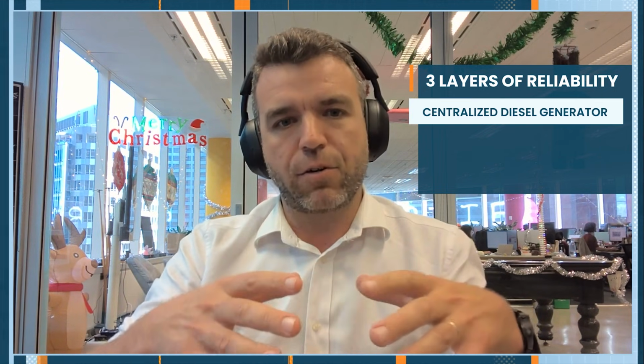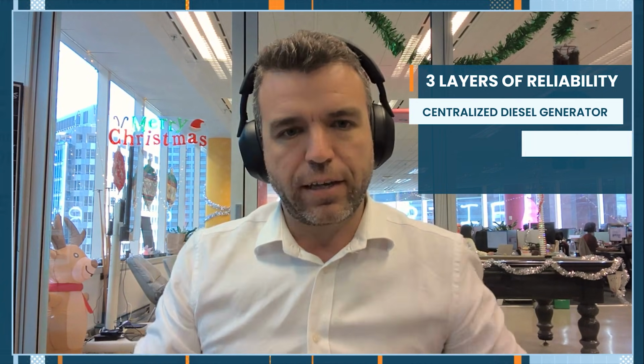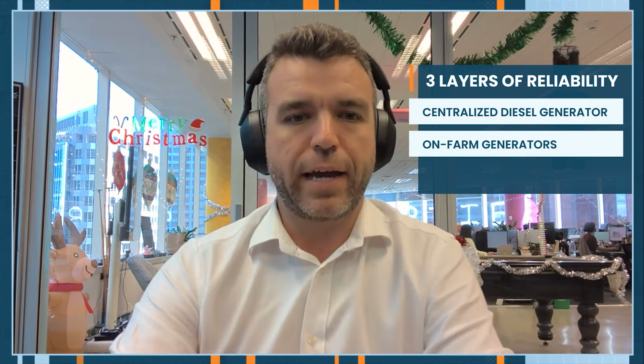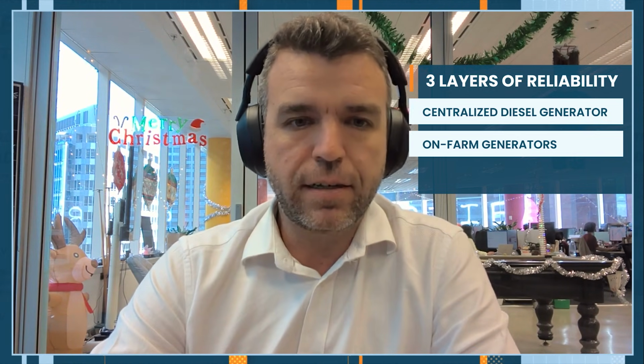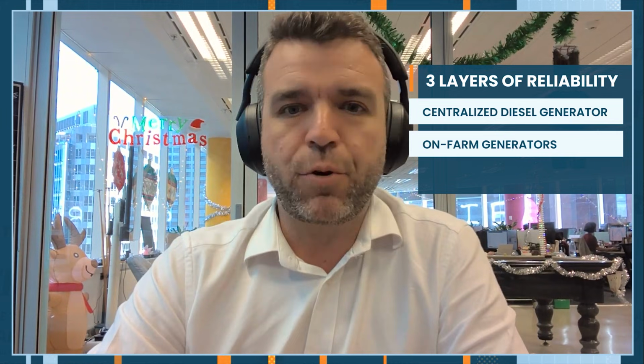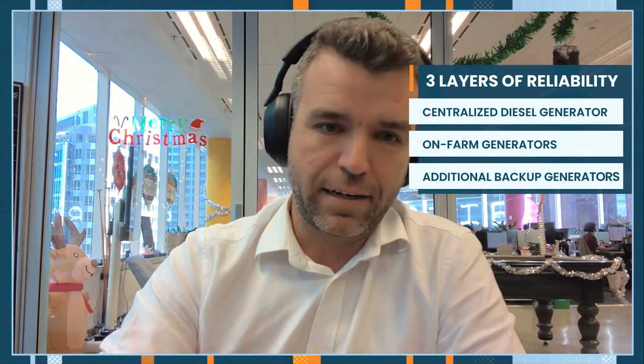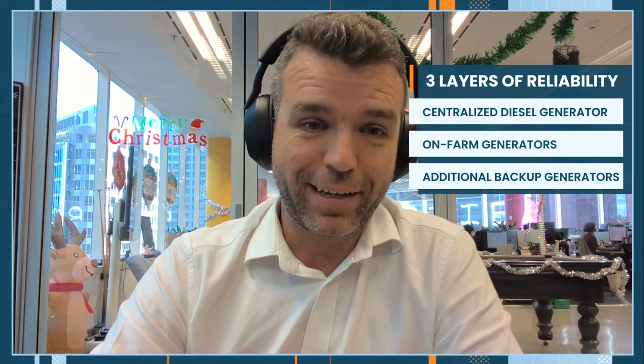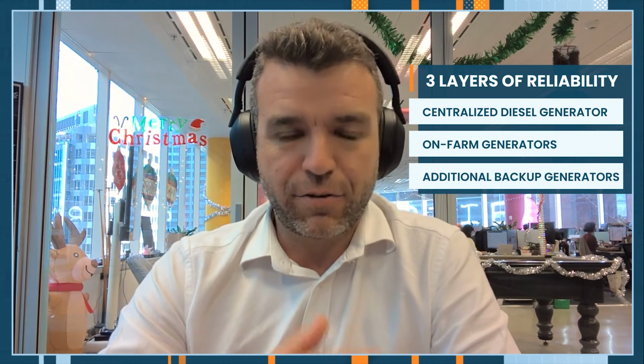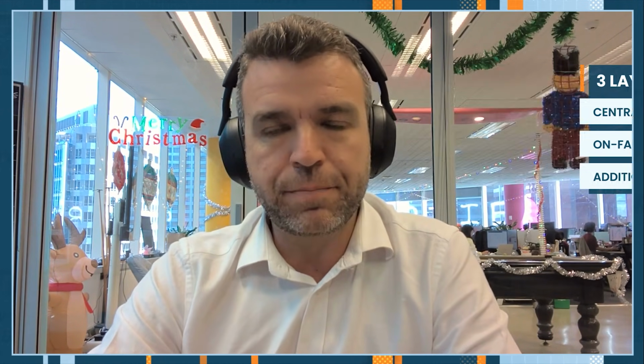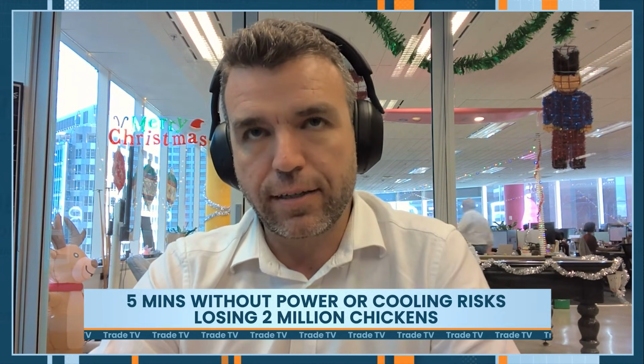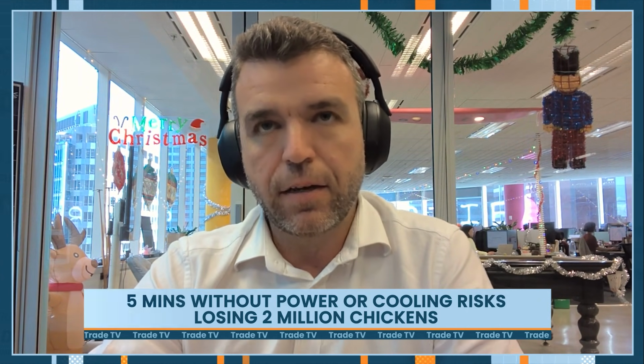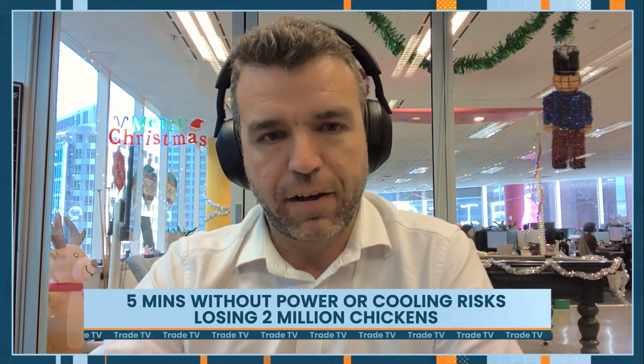Reliability is the key to success here, and having reliable products helps with that. We have a centralized diesel generator at the solar and battery system, and then on the individual farm areas themselves we have another 4 generators as a third point of failure, plus another set of generators just in case everything else turns bad. So there are 3 layers of reliability built into this system, because if the chickens go without cooling and water for more than 5 minutes, we lose 2 million chickens.